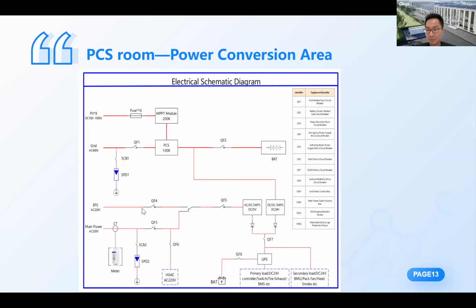What it can do is, for the 100K PCS, every single phase can do 0 to 33 kilowatts of output, regardless of what the other two phases are doing. Our phases work independently of each other. For a three-phase inverter, that would be 100 divided by 3, plus a bit more, I think 5% more. It can do 100 kilowatts divided by 3 per phase, times 1.05. Unbalanced output per phase beyond that might trigger the AC overload on the grid or load side.